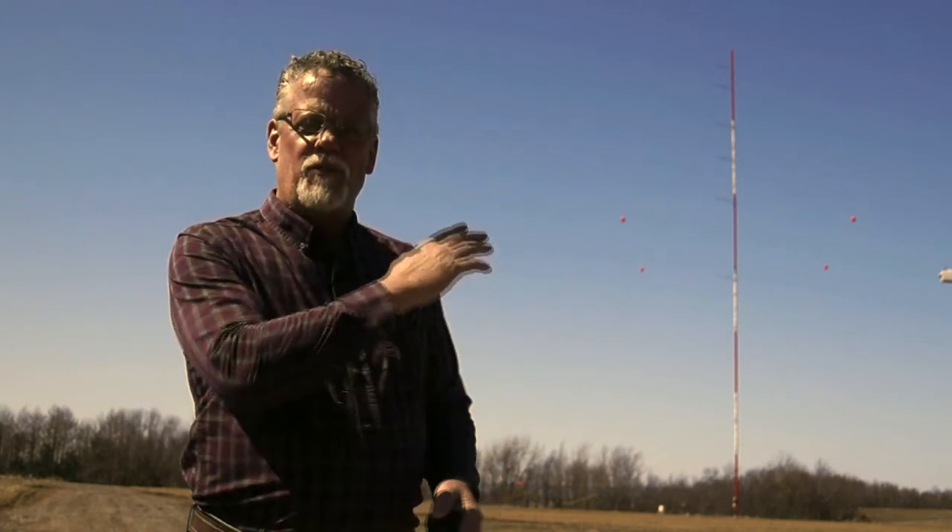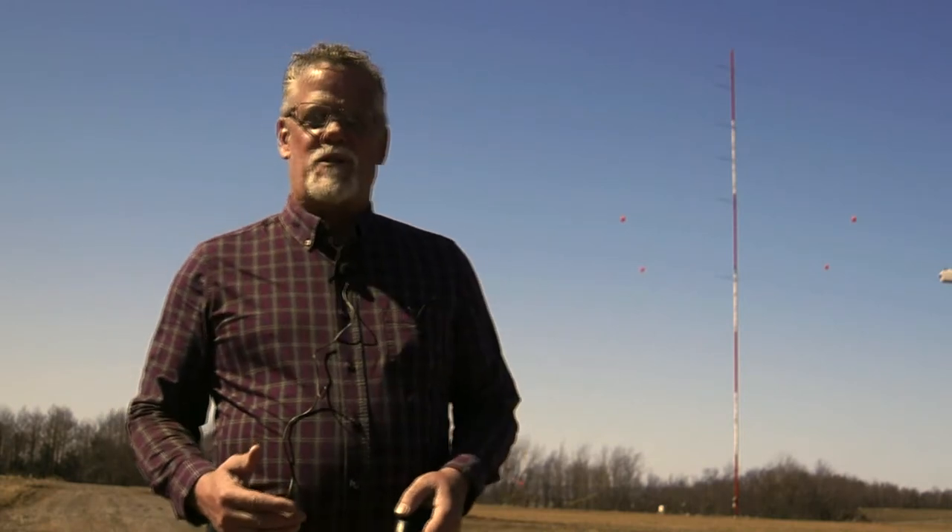Essentially they're weather stations that can measure and record the wind speed and direction, temperature, barometric pressure, humidity, and other data. Each MET mast has booms up at certain levels with anemometers and weather vanes on them. The booms are typically perpendicular to the dominant wind so that the wind can hit the instruments unobstructed by the tower itself.